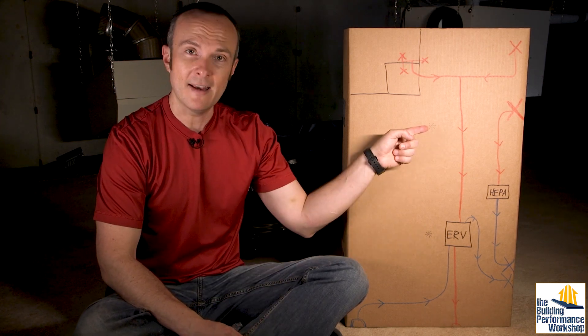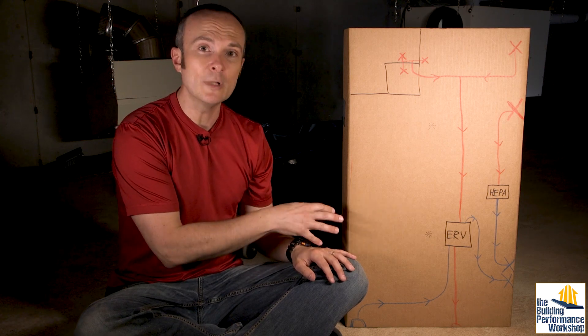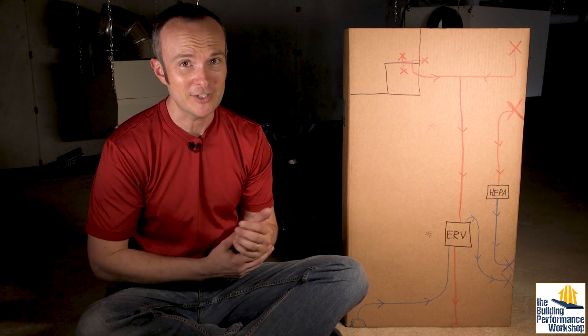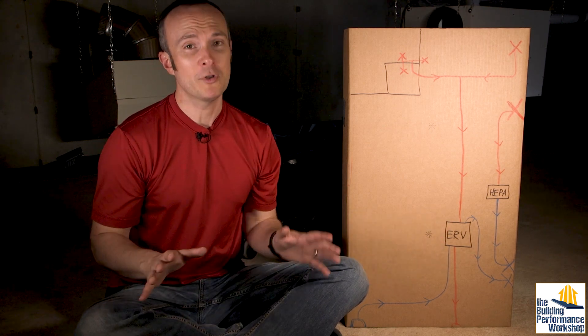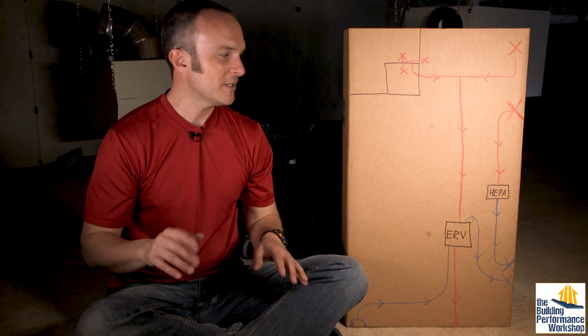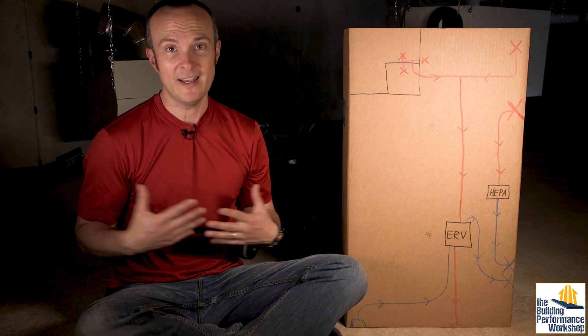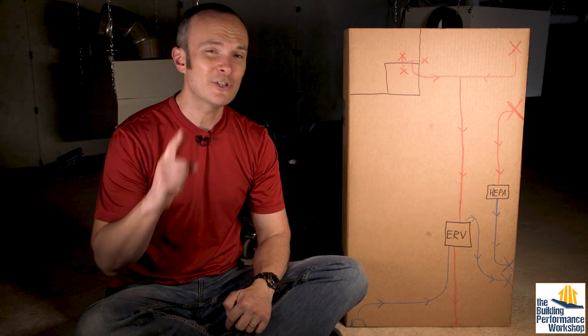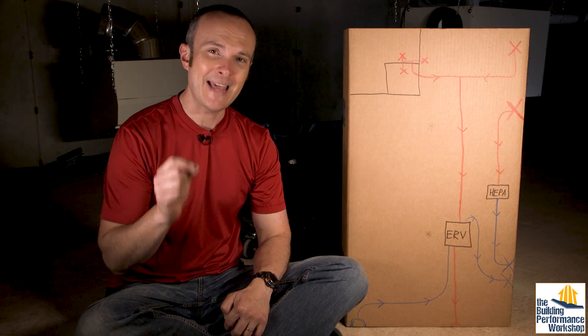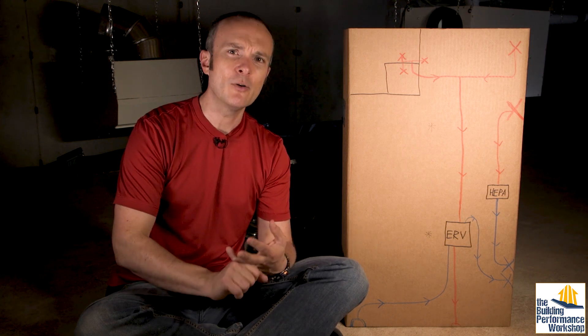In a previous video, I talked about how to use the fact that they blow different rates to induce a pressure differential across the entire space above us, and also incorporate what's going on down here. This crawl space is not going to have a dedicated dehumidifier inside of it — there will be a dehumidifier installed in the space above, an Ultra Air MD33, an in-wall dehumidifier that pulls 33 pints a day. I want to be able to cycle the air in this crawl space up through there so the air down here doesn't get stale over the 100-year life of this house.